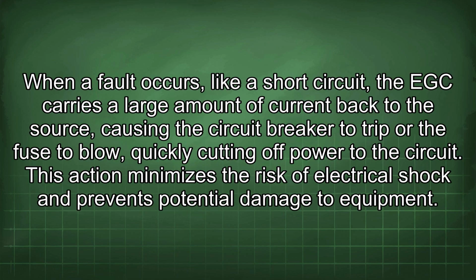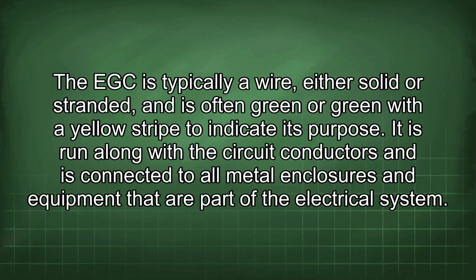When a fault occurs, like a short circuit, the EGC carries a large amount of current back to the source, causing the circuit breaker to trip or the fuse to blow, quickly cutting off power to the circuit. This action minimizes the risk of electrical shock and prevents potential damage to equipment. The EGC is typically a wire, either solid or stranded, and is often green or green with a yellow stripe to indicate its purpose. It is run along with the circuit conductors and is connected to all metal enclosures and equipment that are part of the electrical system.